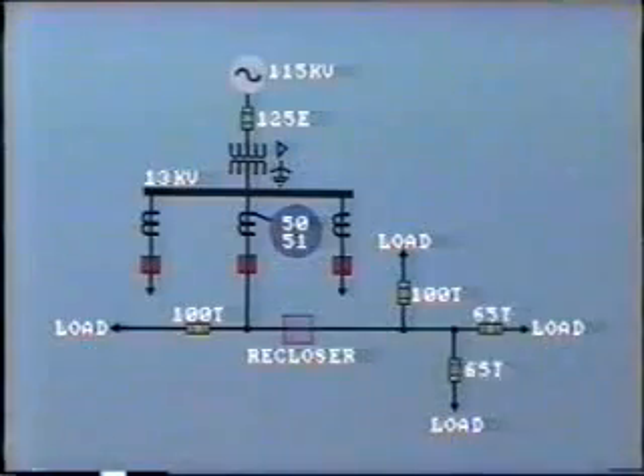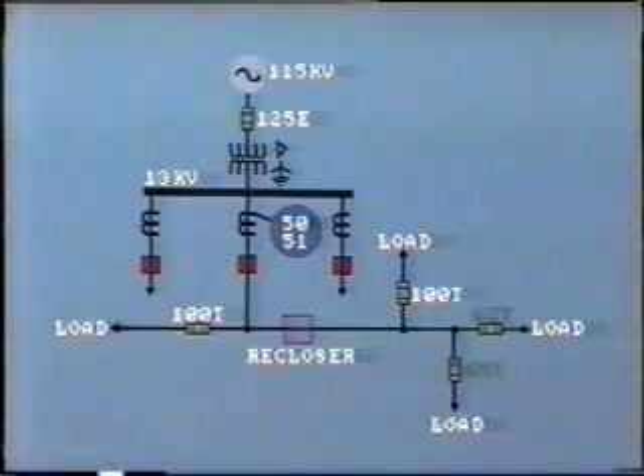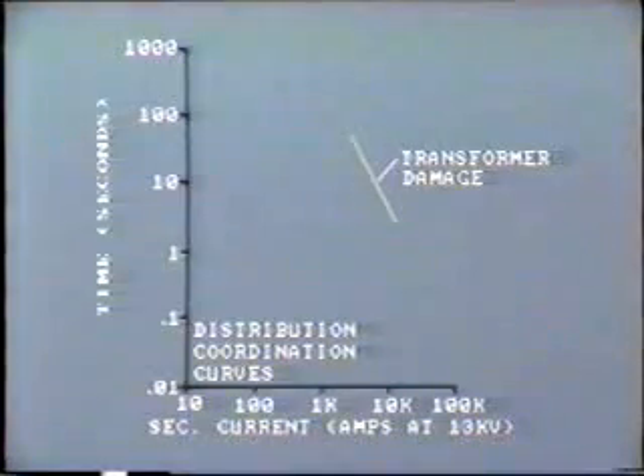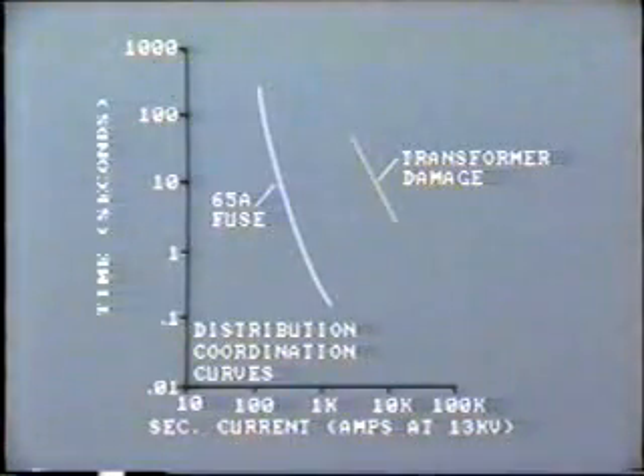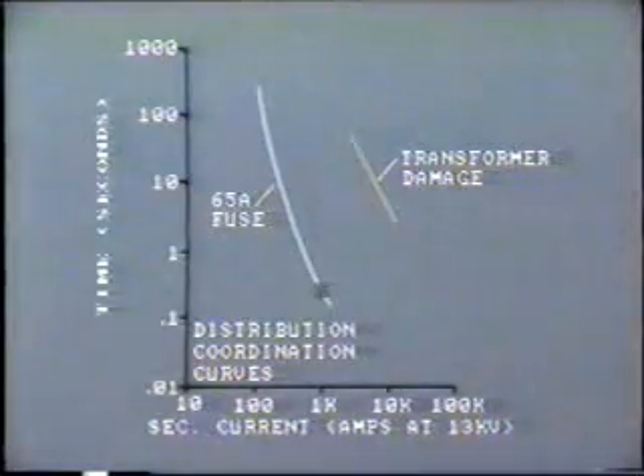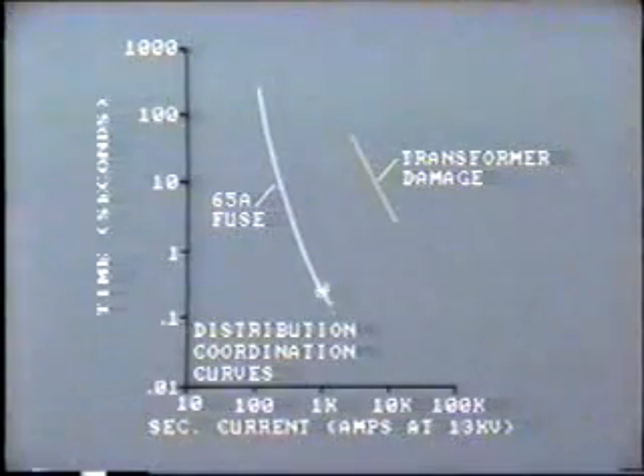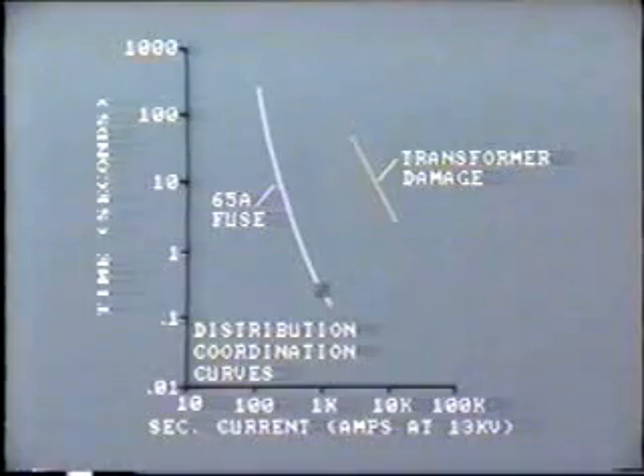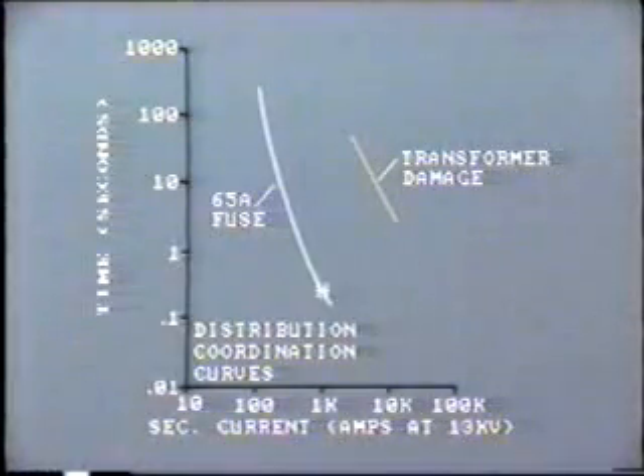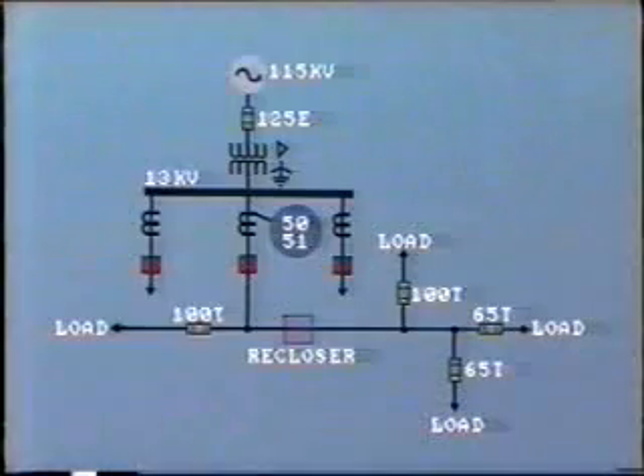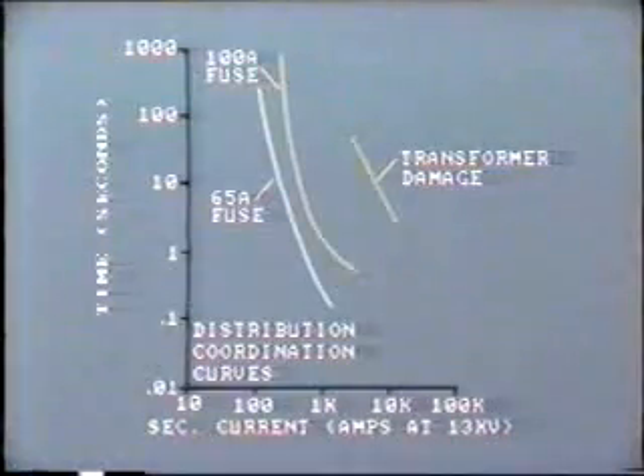At these two locations, 65-amp fuses are installed. The characteristic of the 65-amp fuse is shown on the curve. As an example, this indicates that a current of 1,000 amps in this particular circuit will cause the fuse to melt within about 0.3 seconds. This is long before the high current can cause any damage to the transformer. The same applies to the 100-amp fuses located at these two branches. The fuse characteristic is shown here.